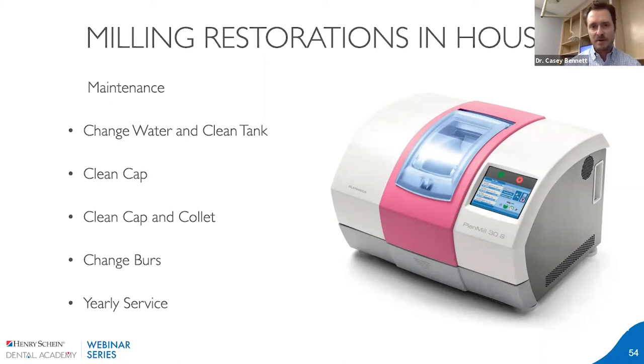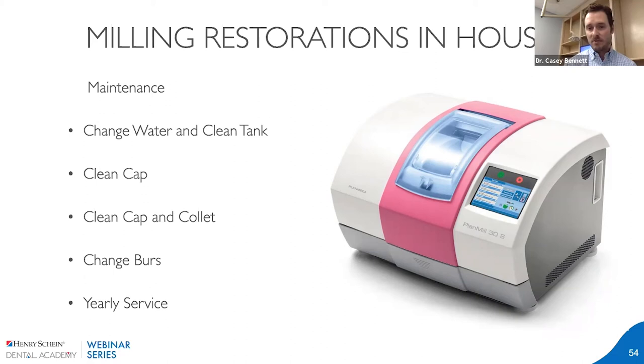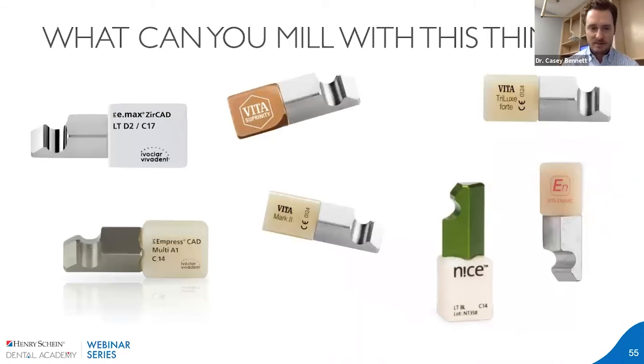The mill also tracks tool breakage and tool wear — it lets you know how many restorations that specific burr has milled. Finally, you'll need some type of yearly service — getting a Henry Schein technician to come out, open everything up, check that the inside of the milling unit is clean, make sure pressure and fluid levels are right, and calibrate it if needed — but that's just once a year. Overall, it's not that much more maintenance. The main thing we do every day is change that water if I'm doing more than three units, because keeping everything lubricated is super important.